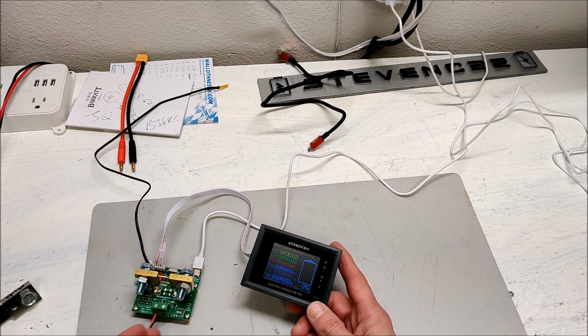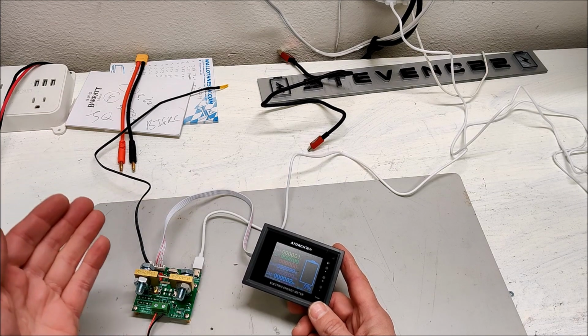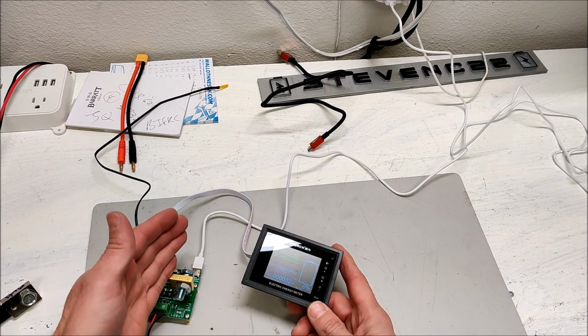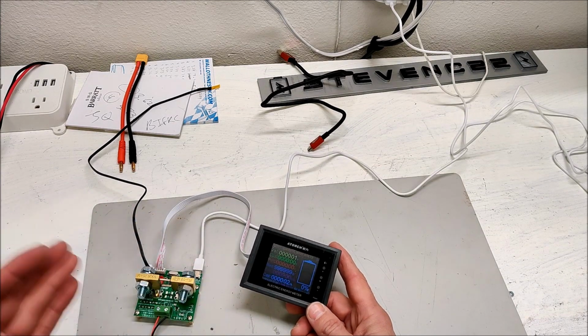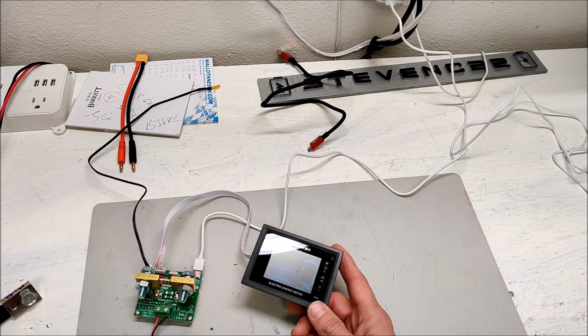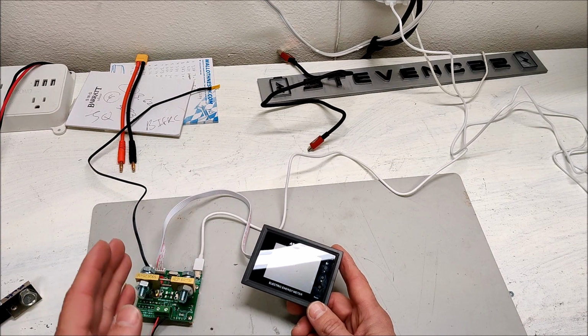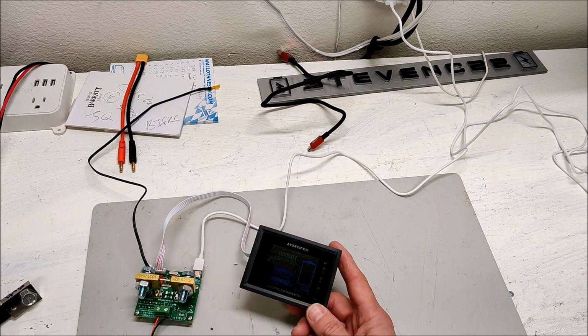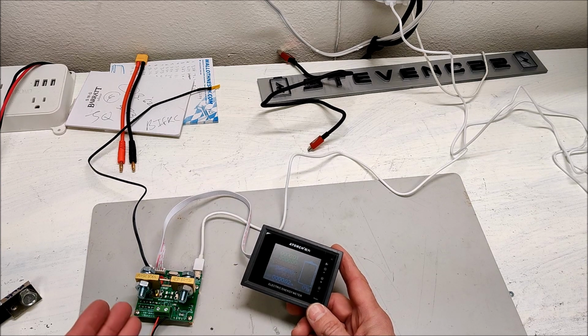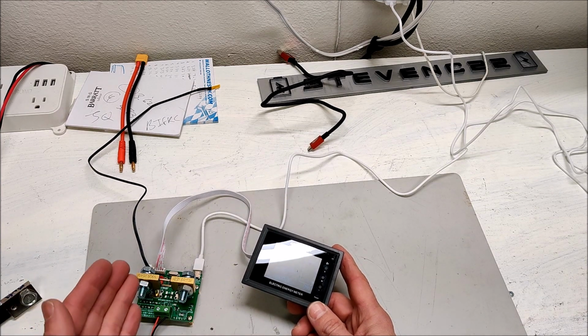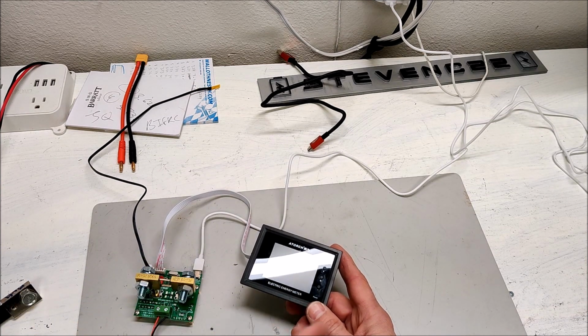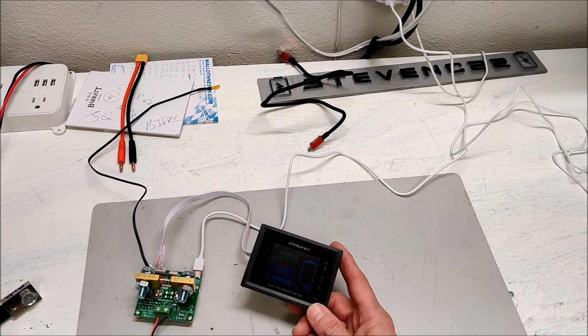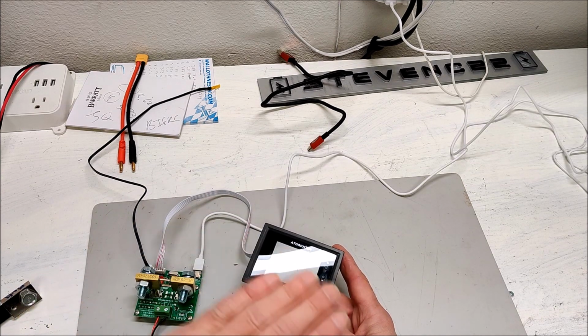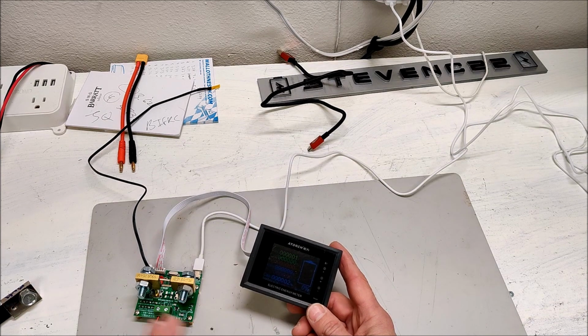These current calculations are mathematical, based on the voltage drop between two points, and there really shouldn't be this kind of issue. If a meter's inaccurate, it should become more and more inaccurate the more current you push through it. This thing starts accurate, is inaccurate in the middle of its range, and then gets accurate again by the high end of the current. So it's got some sort of current curve in it that's weird.